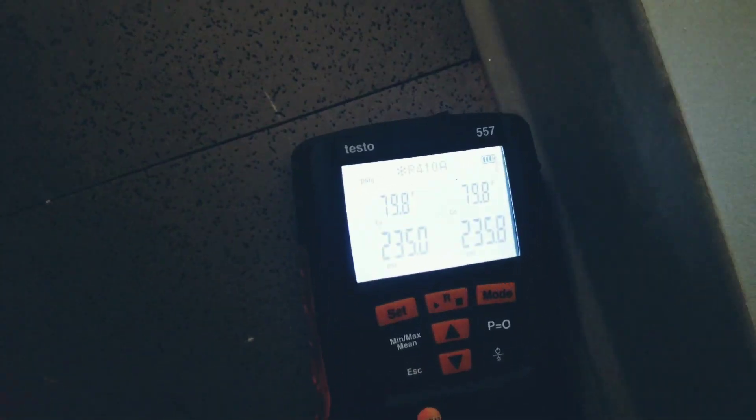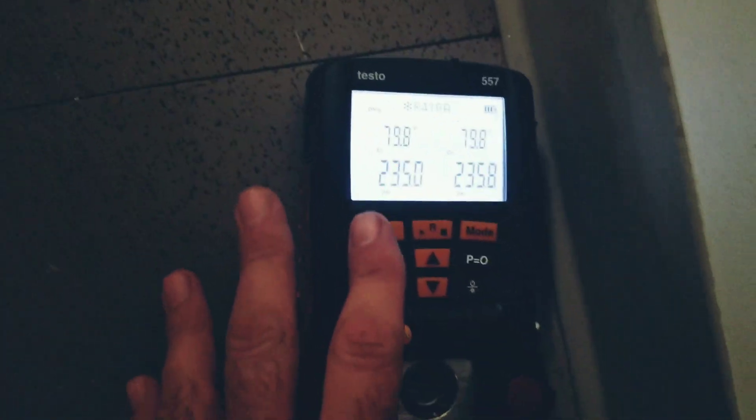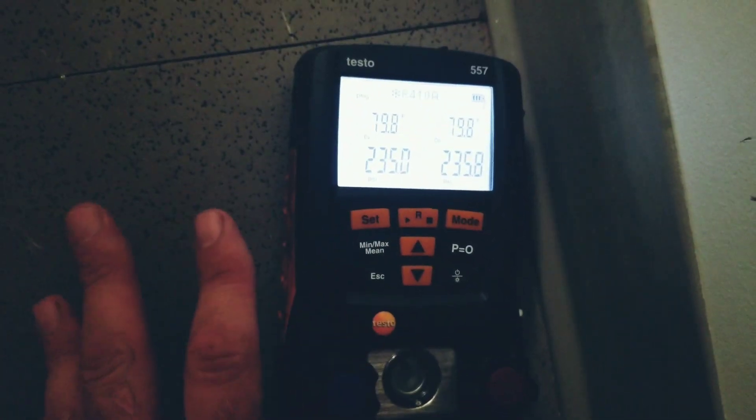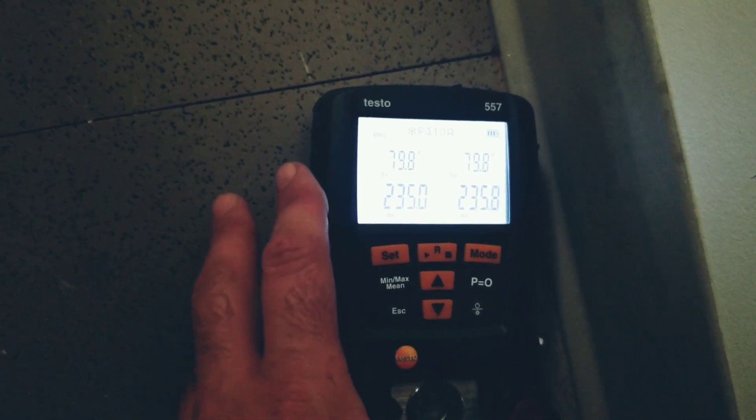Now when I took it apart, I realized that inside we had a low pressure switch that was mounted, and it was cycling on that. I verified that it had low pressure by putting the gauges on and checking, and it was low pressure.